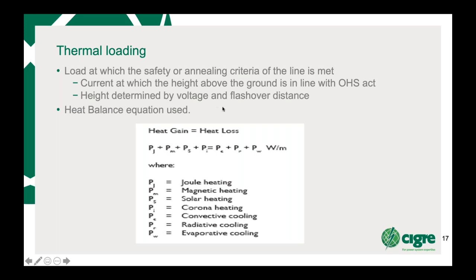To calculate the thermal rating, we use a heat balance equation, where you've got your Joule heat, magnetic heating, solar heating, and ionization or corona heating. Now, magnetic heating is normally included in the Joule effect, so you get one effect there relating to the AC to DC ratio. The ionization or corona heating occurs at high wind and high humidity, where the cooling effect is very high. So the corona heating can be ignored because really you shouldn't be in corona in the first place.